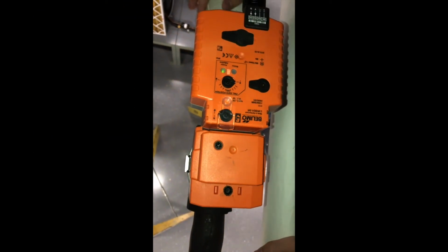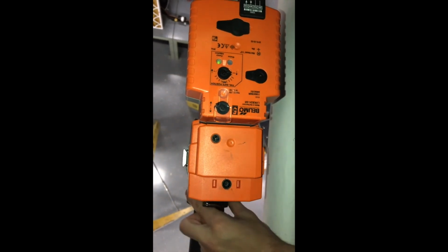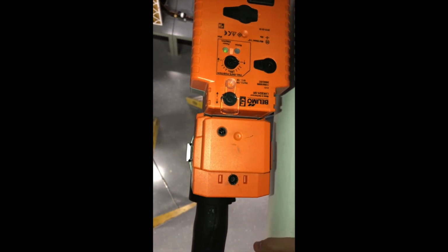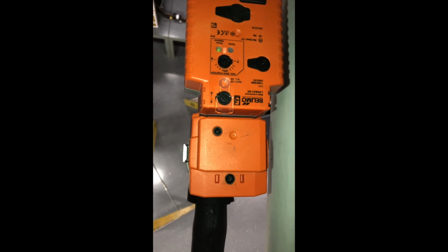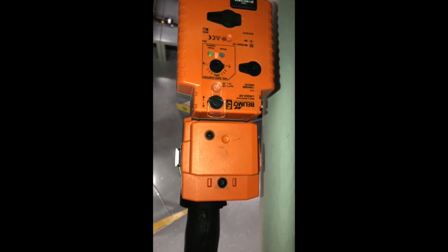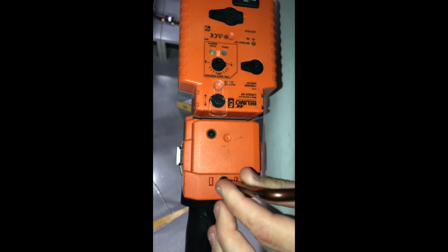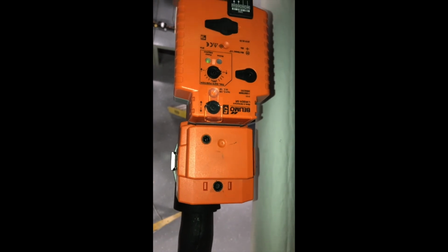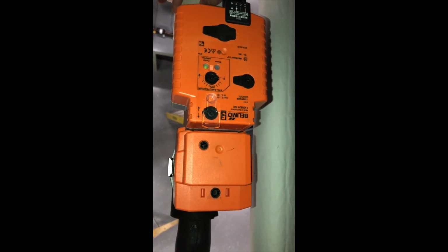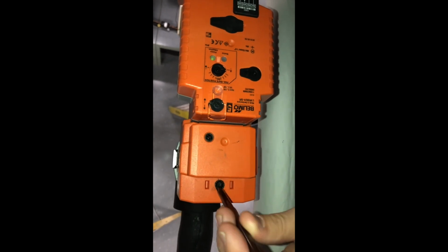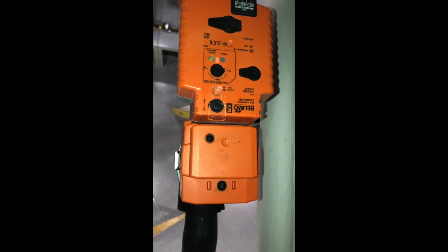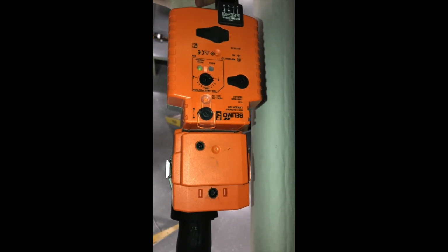So this is your cooling valve. This top part here is the actuator. The valve is actually down here under this insulation. If you take power away from this, it's going to automatically open, but if it does get stuck in the closed position or anything like that, you can remove the power, and then you just stick your Allen key in here and twist it either way to your desired position, and it'll stay right there. It'll then either be open or closed, and you can leave the power off until you figure out what it is. If for any chance you try to turn this and it doesn't want to turn, it's probably seized up, and I would avoid breaking it, and then see about getting a new actuator.